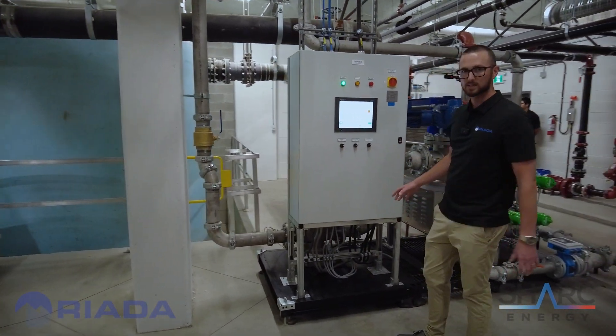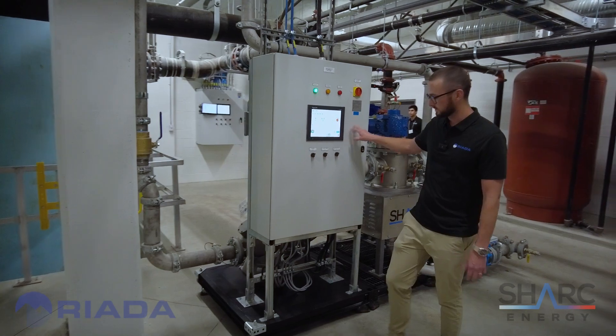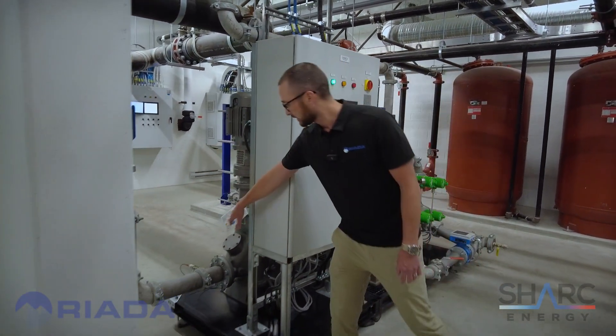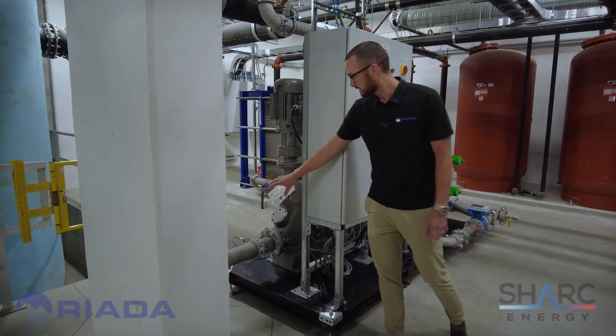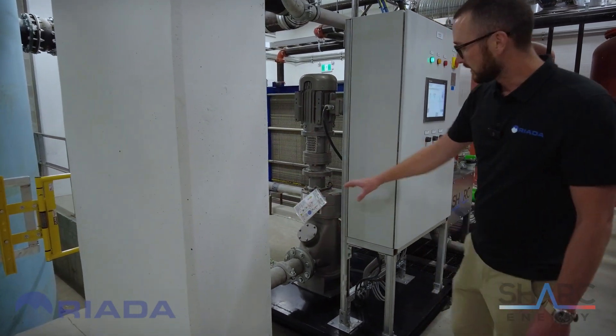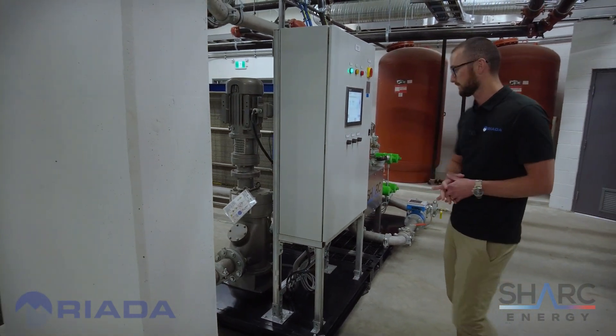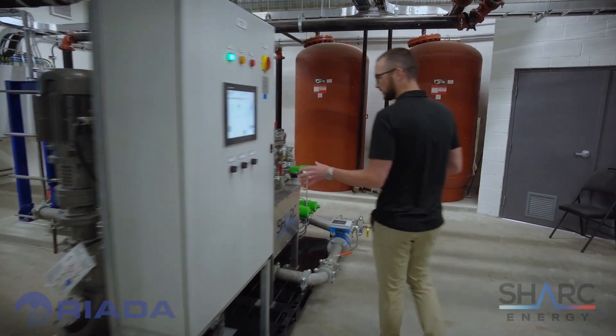As part of the SHARC skid design, we've got our control box with a touch screen control developed by SHARC. Behind here we've got a macerator — the first thing the wastewater hits. Here we take the solids down to a maximum of 20 millimeter size.